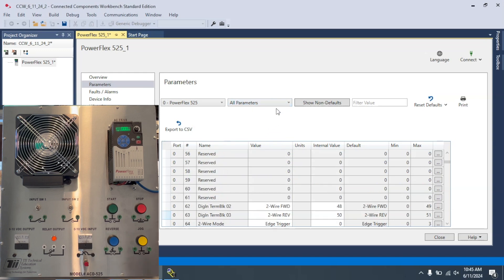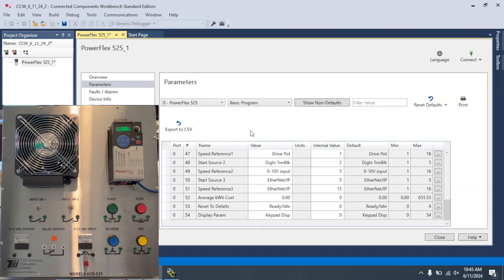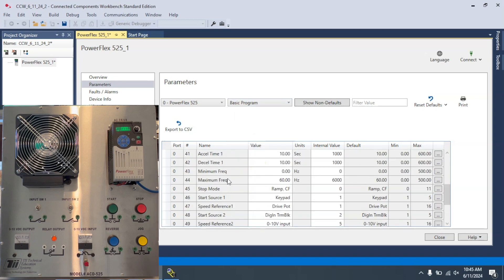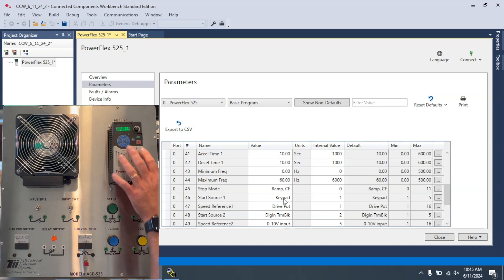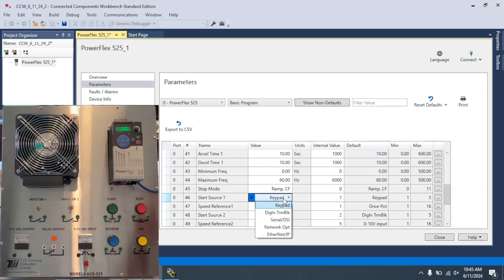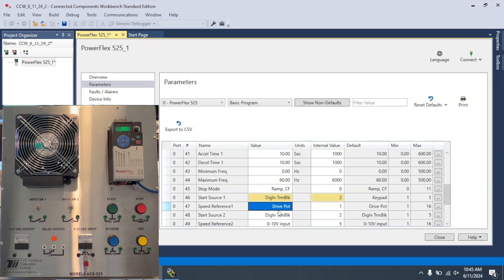The first parameter we want to go to is in the basic programs. That's going to be 46. And right now, the start source is set to the keypad. So I'm going to come here and select Digital Terminal Block and hit Enter. This should change the internal value to 2.